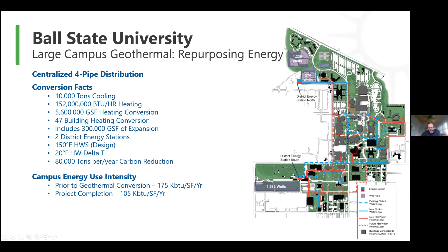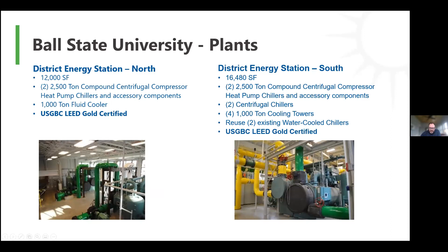You can see in the diagram here, there's the south plant, the north one is way up here, along with large well fields immediately adjacent to both central energy plants. We've converted the buildings to a design heating hot water temperature of 150 degrees Fahrenheit. We'll talk about how that temperature was selected. The north and south plants aren't huge in footprint, but have relatively large capacity with large centrifugal compressor machines. The south plant also has additional cooling tower capacity to ensure system reliability for the campus.